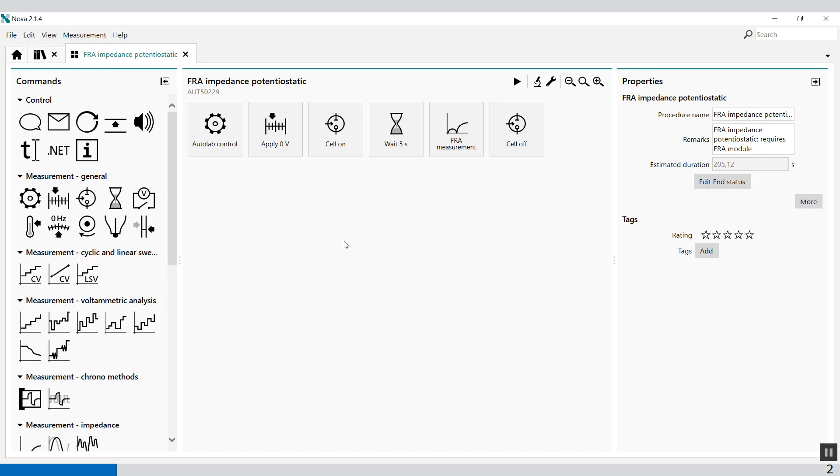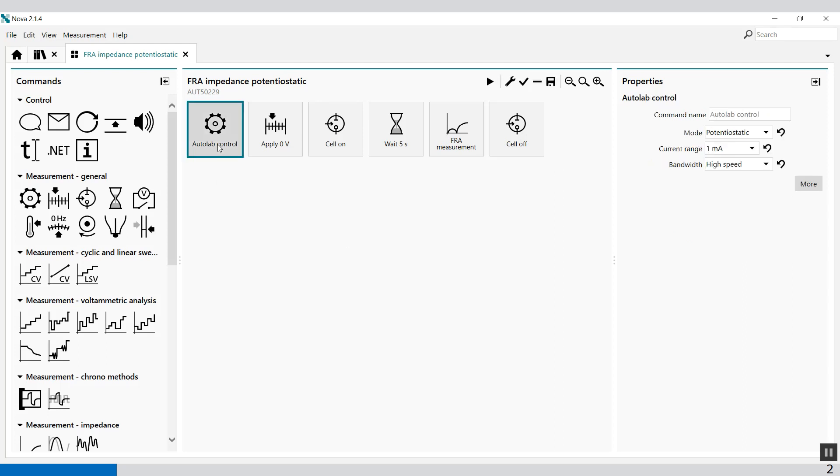The procedure is opened. The default FRA impedance potentiostatic procedure provides an example of an electrochemical impedance spectroscopy measurement in potentiostatic conditions. The potentiostatic mode is selected at the beginning of the procedure using the Autolab control command. In the Autolab control command you can select between potentiostatic or galvanostatic, but in this case it's potentiostatic.